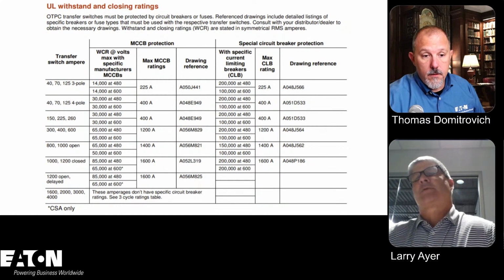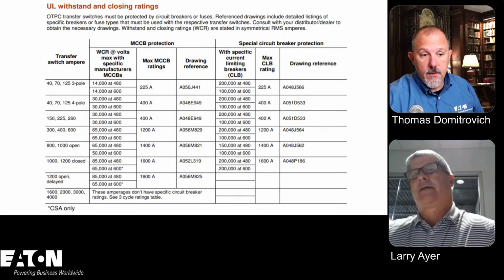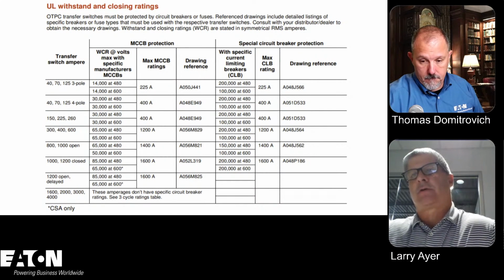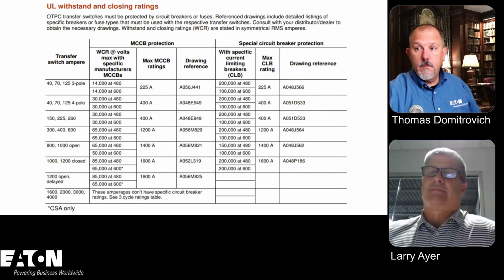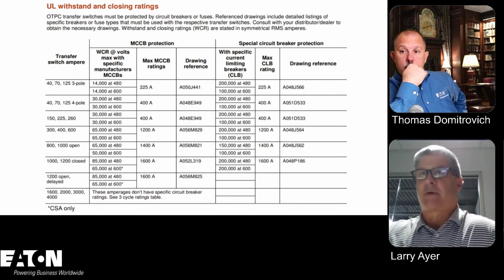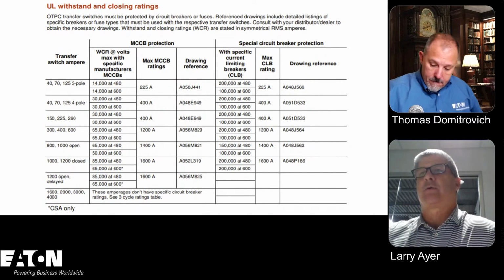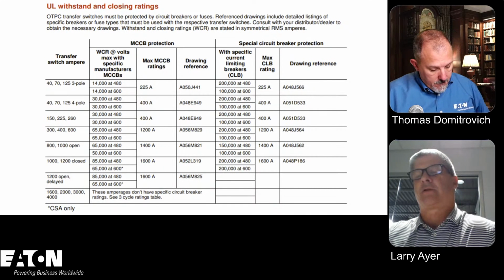Right, and so the reason we put this slide in here was more or less that typically most people are going to go out and get a listed fire pump controller, or they're going to get a listed fire pump transfer switch. Maybe it's a combination, or you're going to get two separate enclosures.